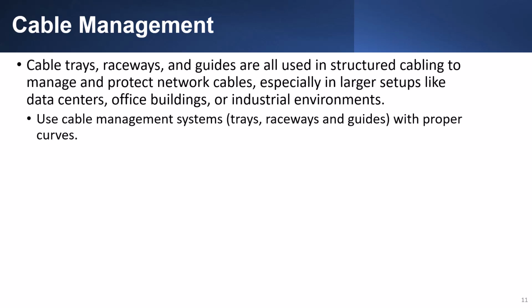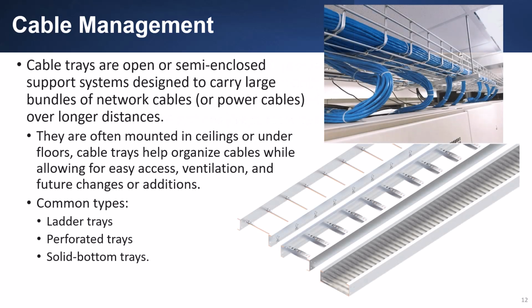Cable trays, raceways, and guides are all used in structured cabling to manage and protect network cables, especially in larger setups like data centers, office buildings, or industrial environments. Use cable management systems that includes trays, raceways, and guides with proper curves. Cable trays are open or semi-enclosed support systems designed to carry large bundles of network cables or power cables over longer distances. They are often mounted in ceilings or under floors. Cable trays can help organize cables while allowing for easy access, ventilation, and future changes or additions. Common types include ladder trays, perforated trays, and solid bottom trays.